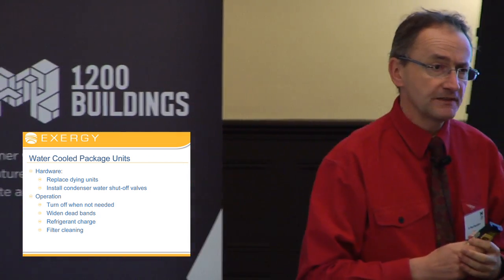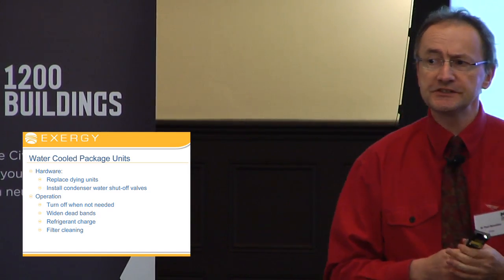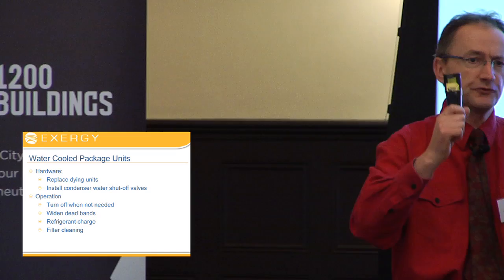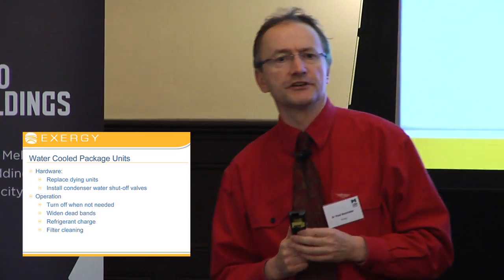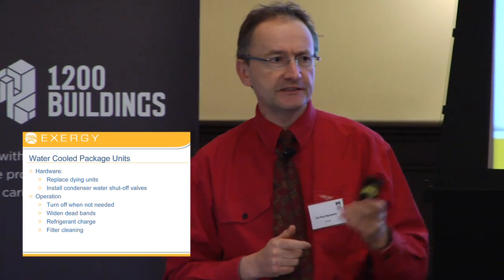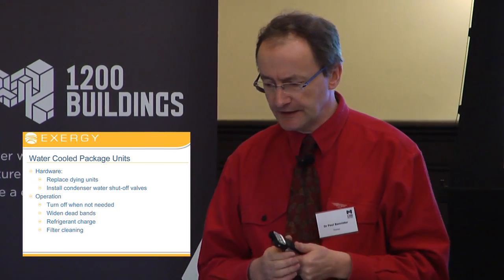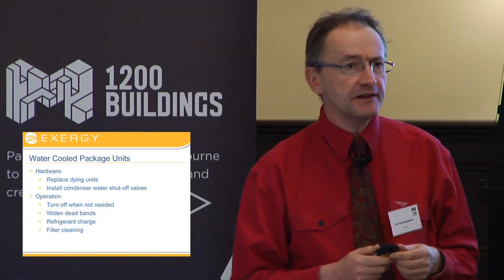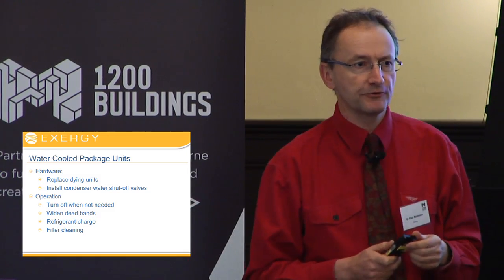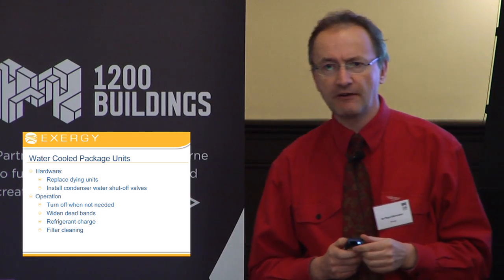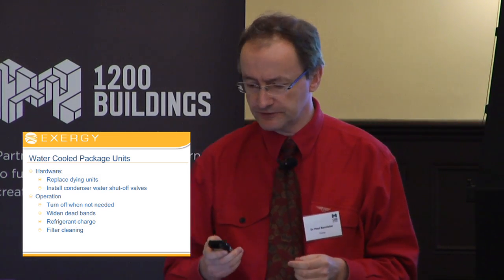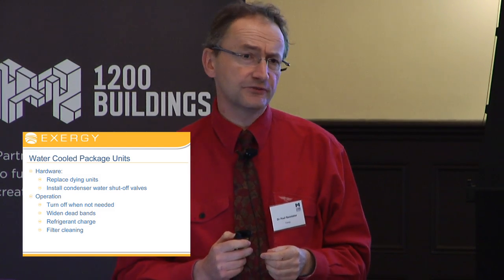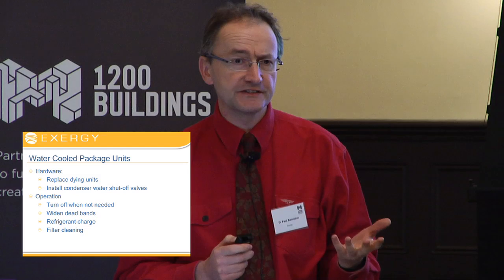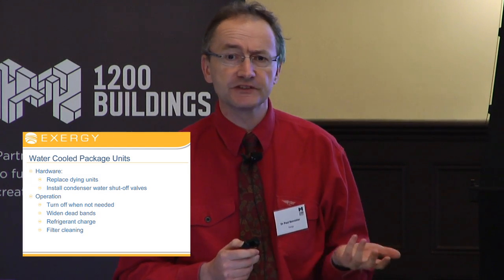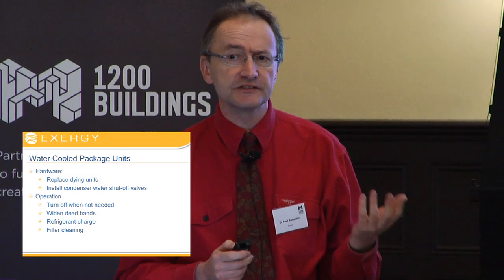Refrigerant charge. A great US statistic: 70% of rooftop air conditioners have the wrong refrigerant charge. We tested that on a building in Liverpool, in Sydney, and the answer was 90% had the wrong refrigerant charge. So you can pretty much guarantee that if you check, you'll find the refrigerant charge is wrong. And clean the filters. People tend to look at these things as low maintenance systems, and so the filters get dirty, and they cease performing.